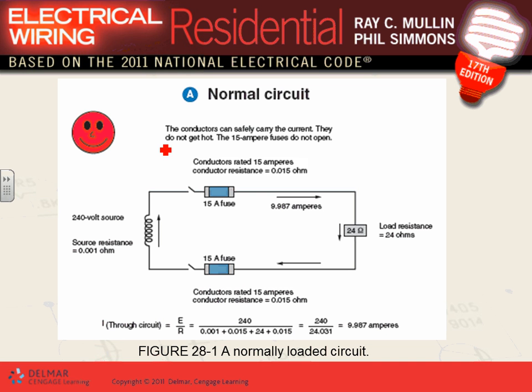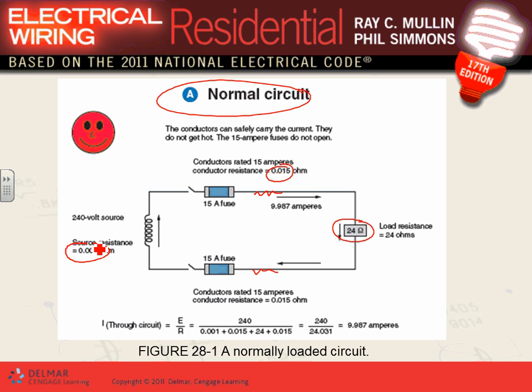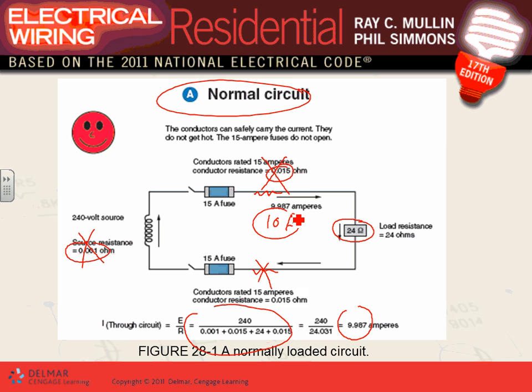Here's a normal circuit condition example. I have a 24-ohm load and a 15-amp fuse, phase-to-phase at 240 volts. Note the impedance of the load, the impedance of the conductors, and the impedance of the source. When you apply Ohm's law — dividing the voltage by all the impedances in series — you get approximately 10 amps being pulled out of a 15-amp circuit breaker. Good to go; it can run forever.